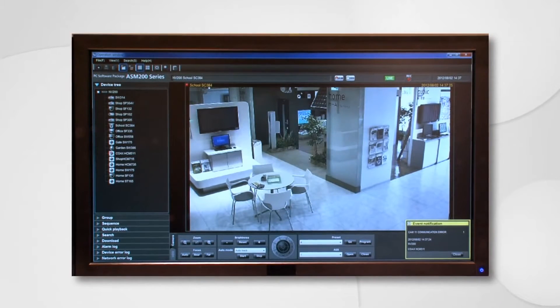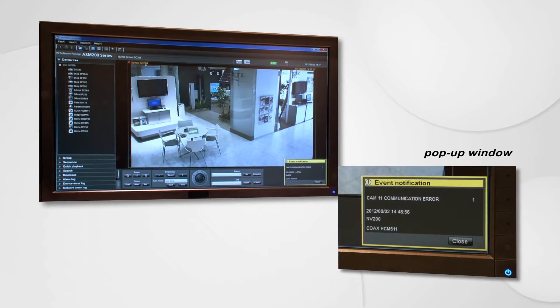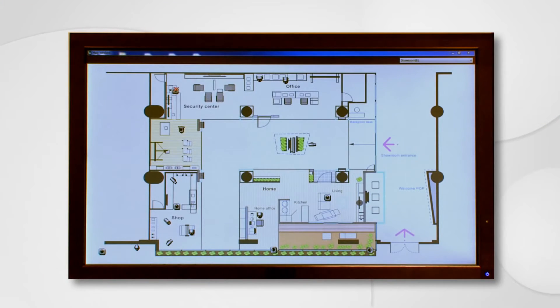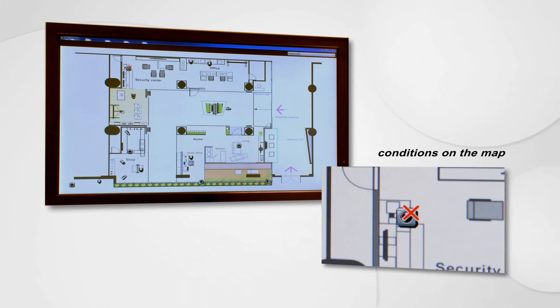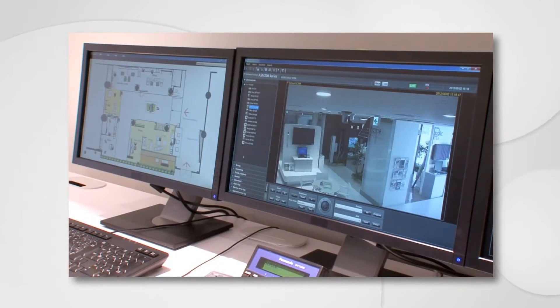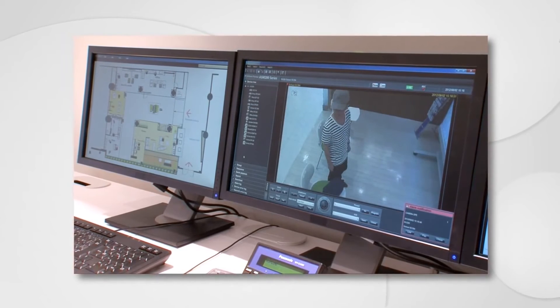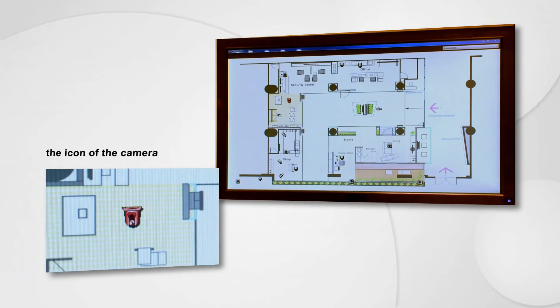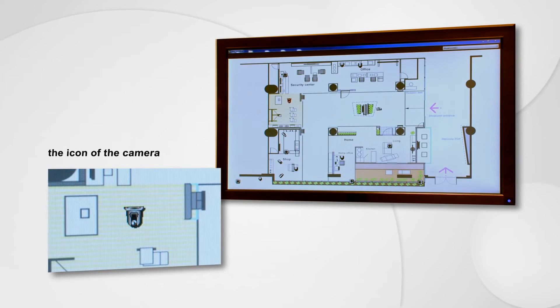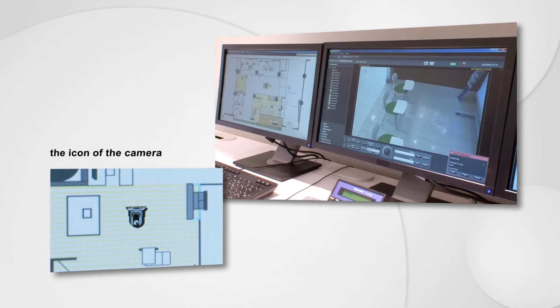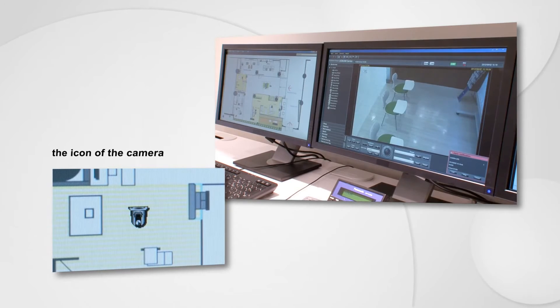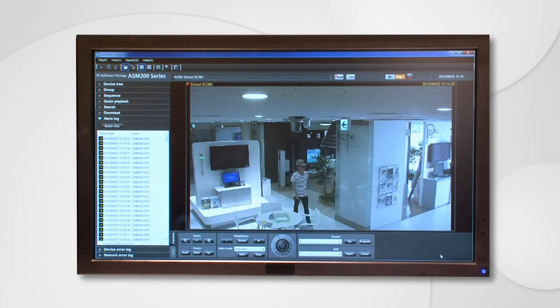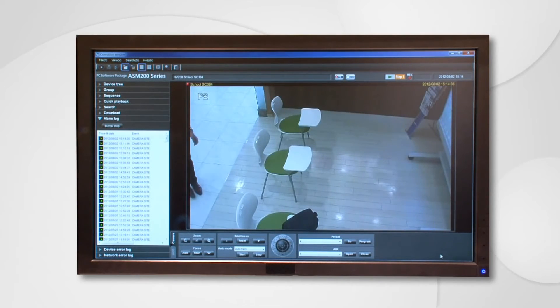The event notification function displays a pop-up window and an alarm sound occurs in case communication with cameras or recorders is interrupted due to malfunction of the equipment or network, and also displays the conditions on the map, making it possible for operators to confirm the situation and seek a solution at an early stage. If a camera or recorder detects an alarm, it notifies the operator by displaying a pop-up window or alarm sound. Also, the icon of the camera that detected the alarm on the map screen will flicker to quickly indicate the place where the problem occurred. Clicking the flickering icon of the camera changes the screen to its real-time screen. At the point of time when an alarm occurred, its recorded image can be confirmed on the spot. The conditions at the time of occurrence can be confirmed instantaneously and measures can be taken quickly.